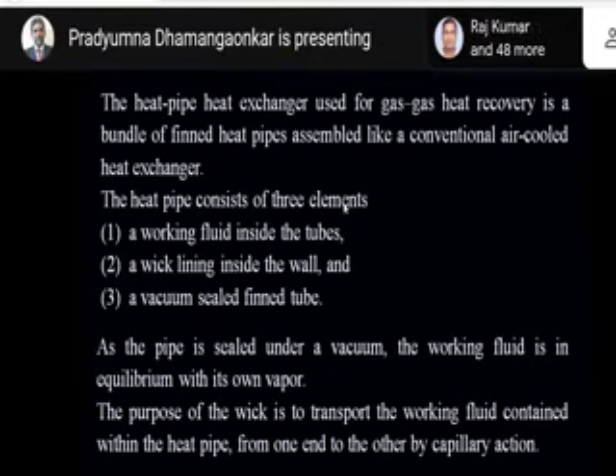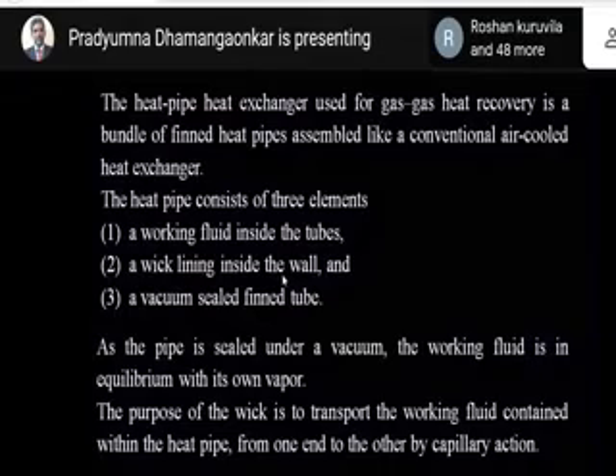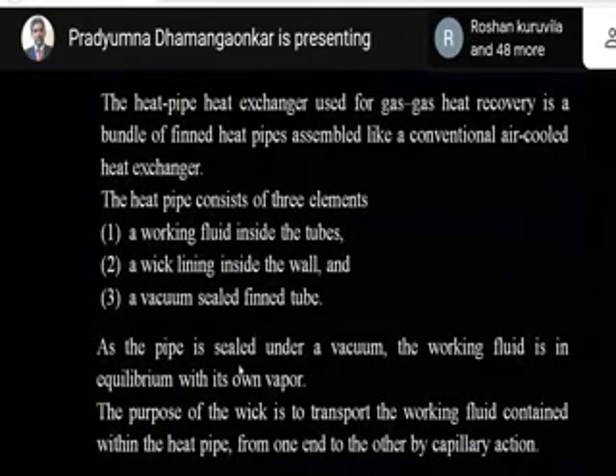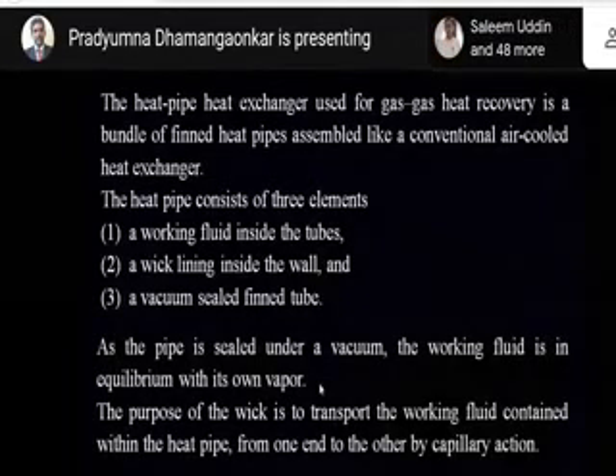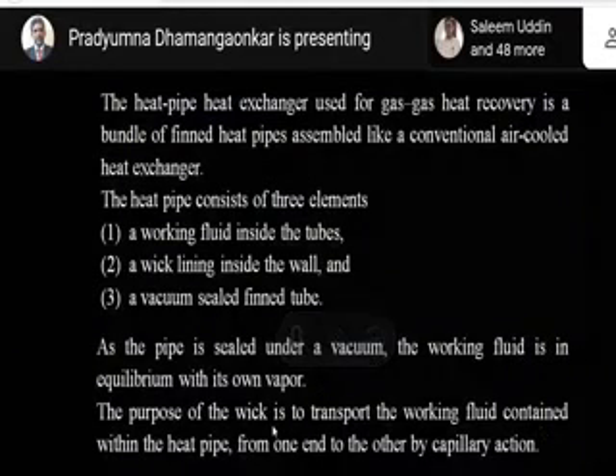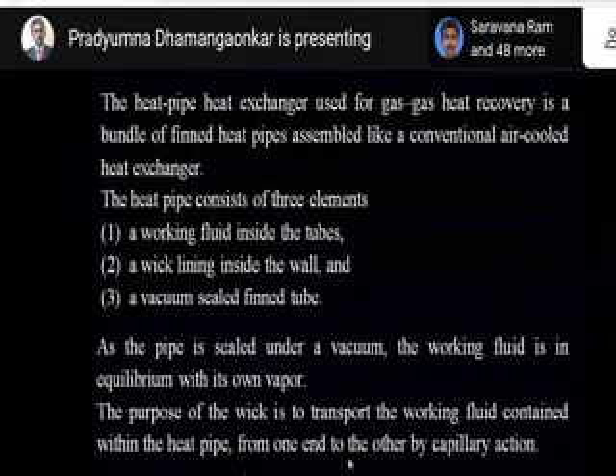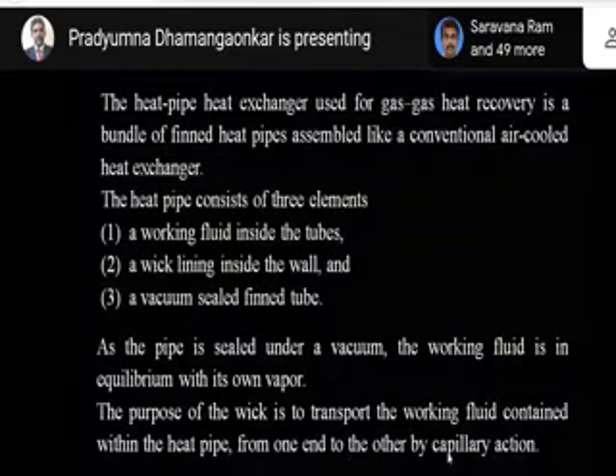The heat pipe consists of three elements. One is the working fluid inside the tube. Second is the wick lining inside the wall, through which the fluid gets condensed and moves. Third, a vacuum-sealed fin tube. As the pipe is sealed under a vacuum, the working fluid is in equilibrium with its own vapor. The purpose of the wick is to transport the working fluid contained within the heat pipe from one end to the other by capillary action.